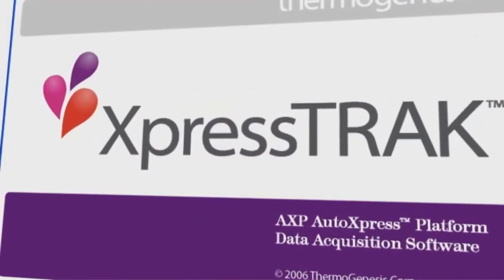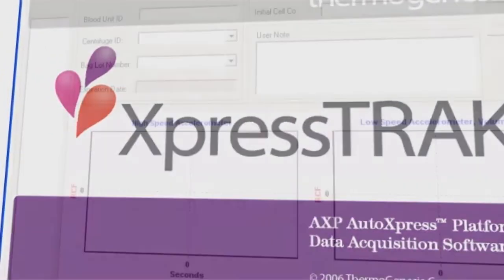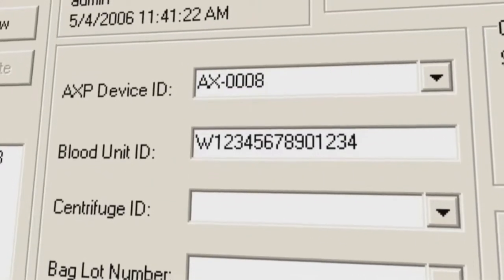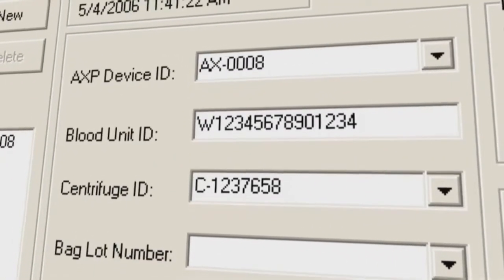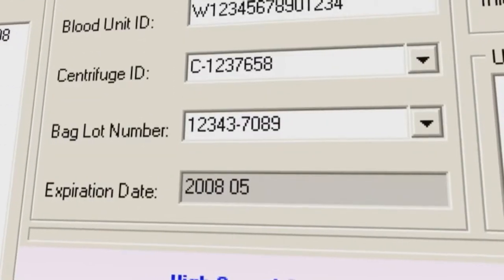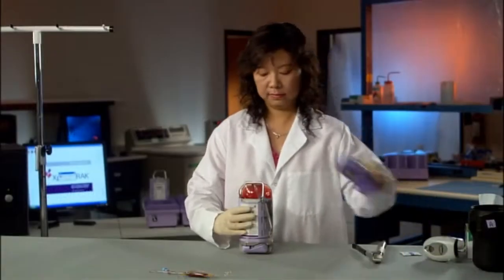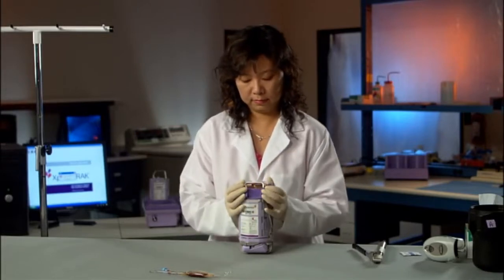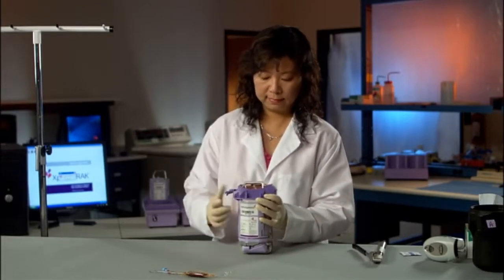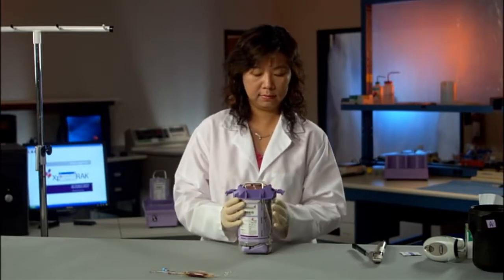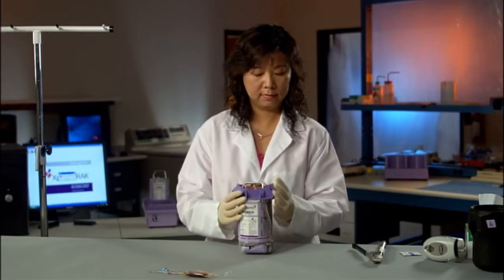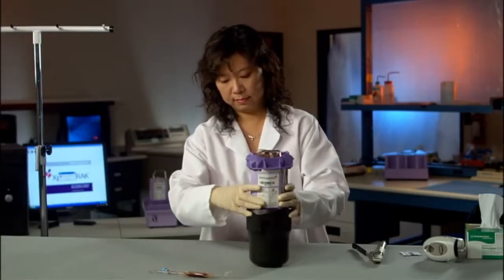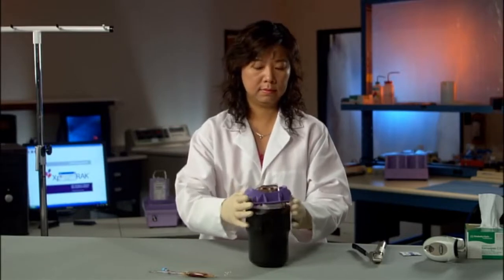Open a sample profile in XpressTRAK by scanning the device ID, blood unit ID, centrifuge ID, and processing set lot number. Determine the weight of the device and balance it with another device using the weight compensation cap or use the specially designed counterweight. The cap can be used to house additional balancing weights. Place each device in a centrifuge bucket, making sure that the left and right edges of the RBC bag are tucked beneath the flanges of the RBC cavity.